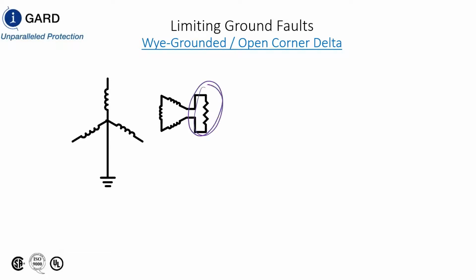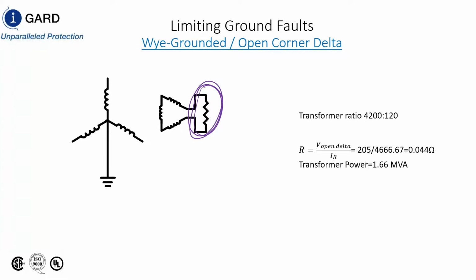A Y-grounded open corner delta. This resistor over here limits the fault current, and you typically would not use this example for a low resistance grounded system, and I'll explain why. Typically you're going to have, okay, this is a 5 kV example, so 4200 to 120 volt transformers. When you have a fault, you're going to develop 205 volts across this resistor, and that resistor is going to limit the fault current.